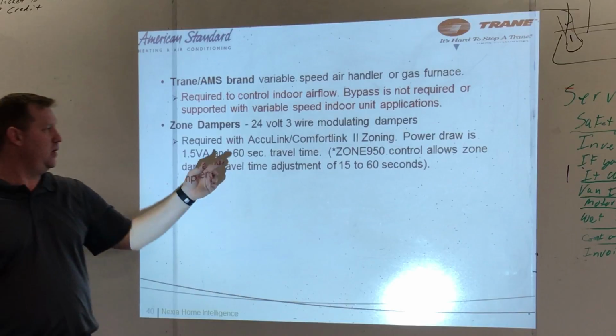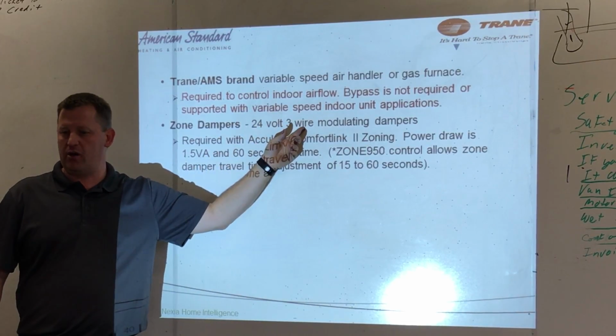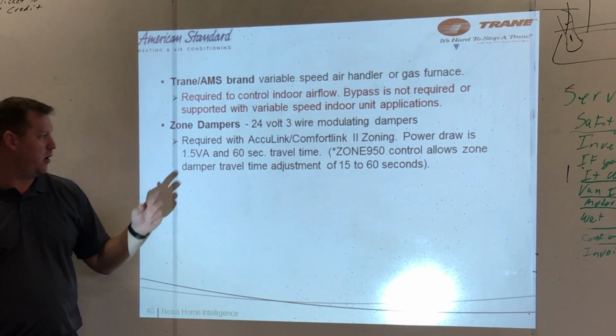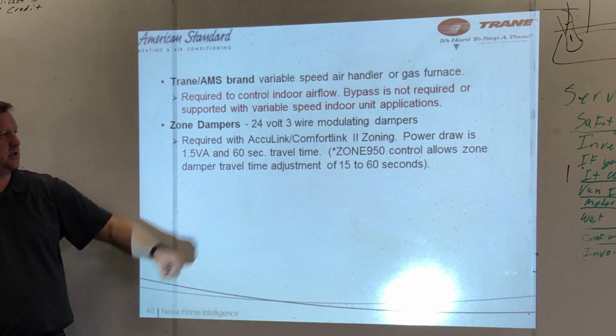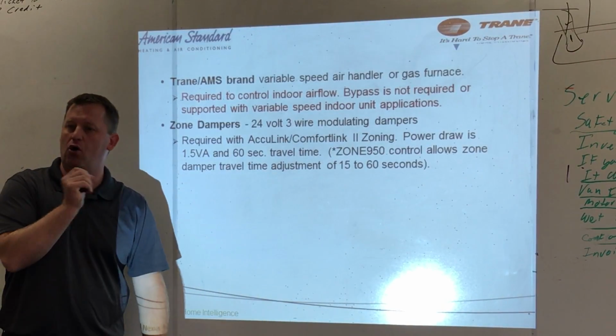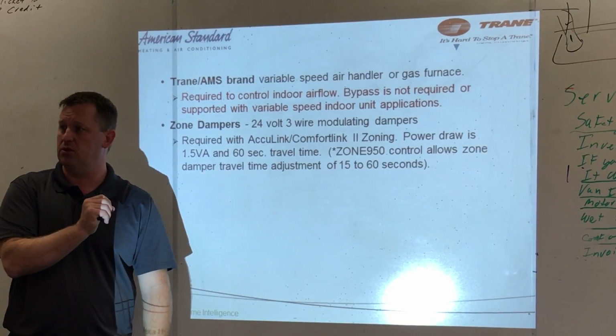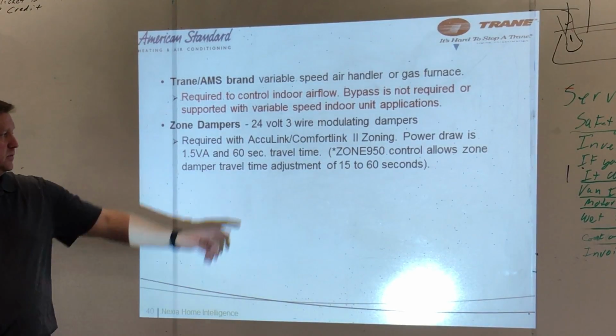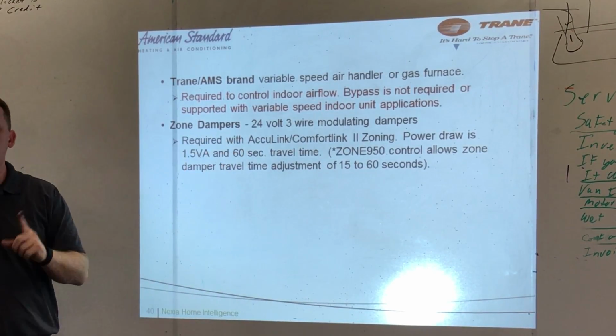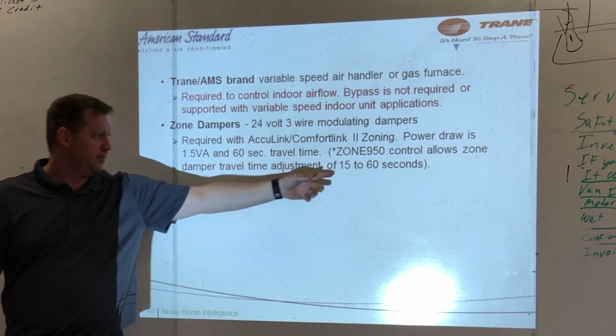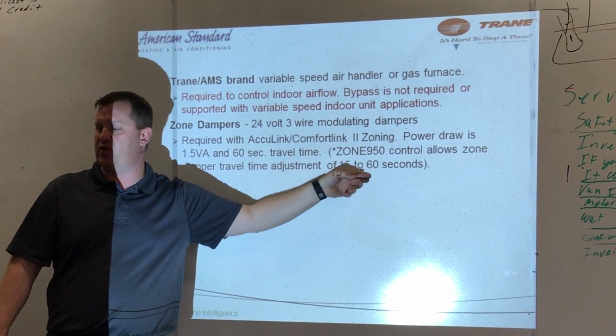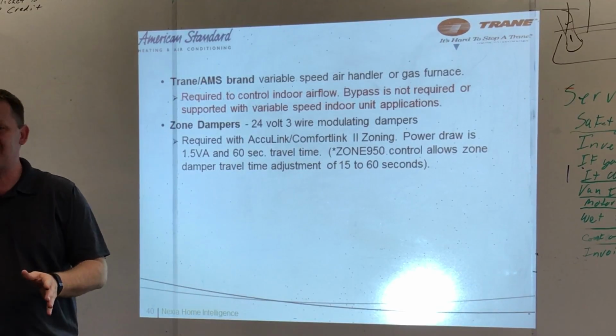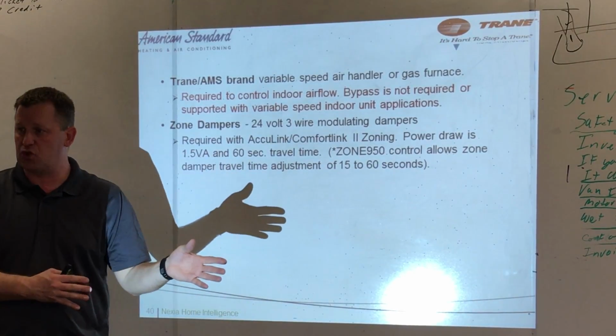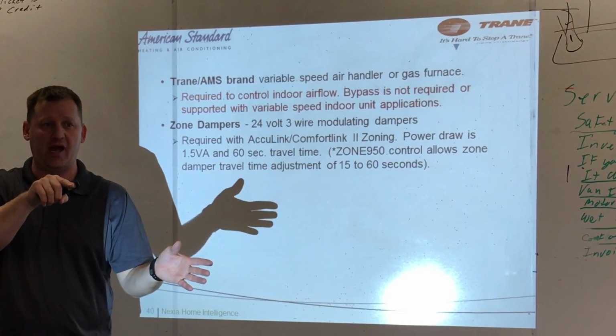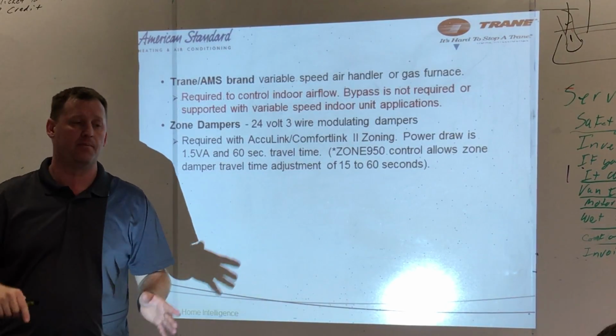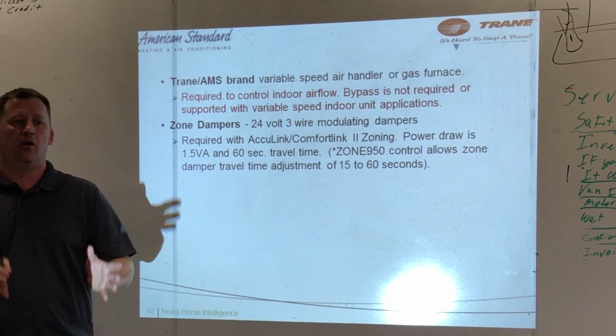Zone dampers have to be 24 volt 3-wire dampers, power open, power close. On ours, they're 1.5 VA, 60 seconds. Including our old dampers, they're the same. Okay? 60-second travel time. We can use someone else's dampers because the travel time is adjustable, 15 to 60 seconds. If you use somebody else's dampers, all the dampers have to have the same travel time. And it's going to be stamped right on the damper, the travel time. Okay? But they all have to be the same.